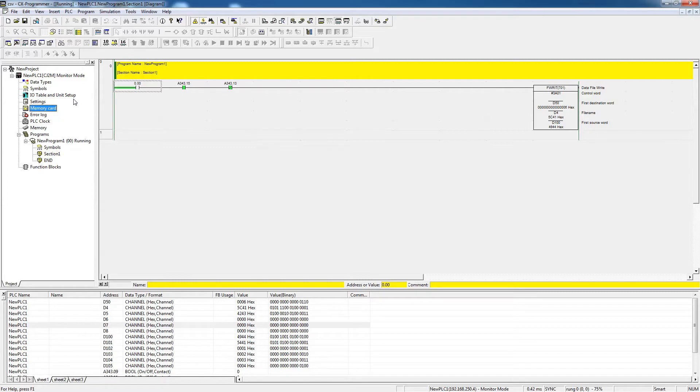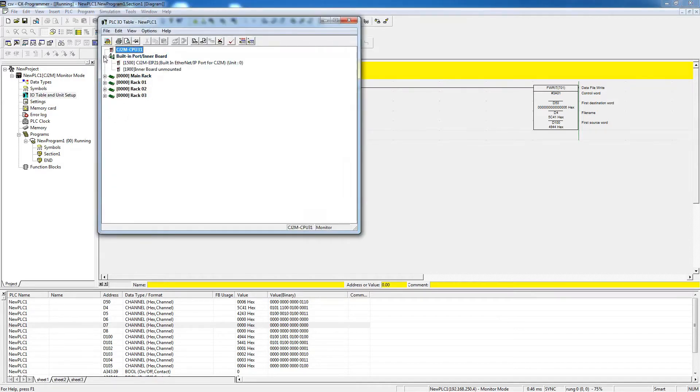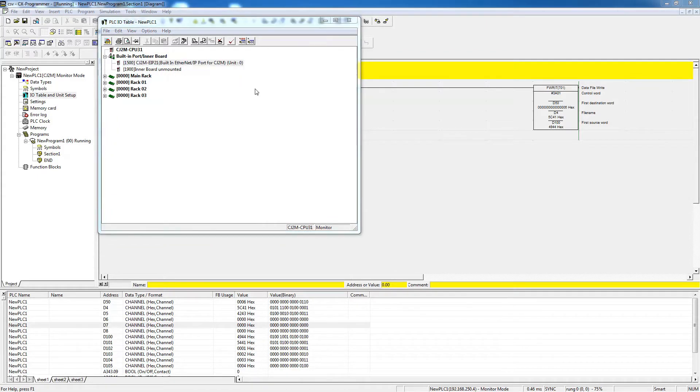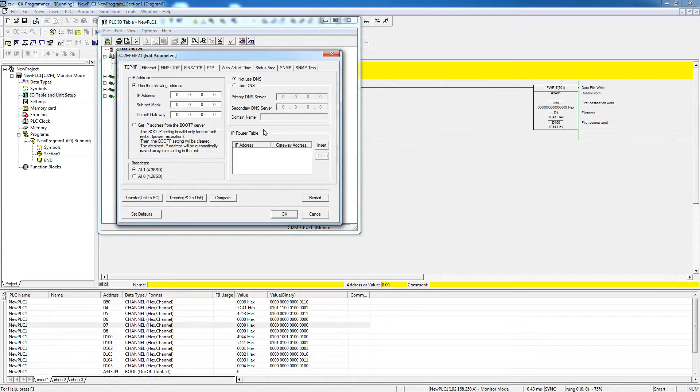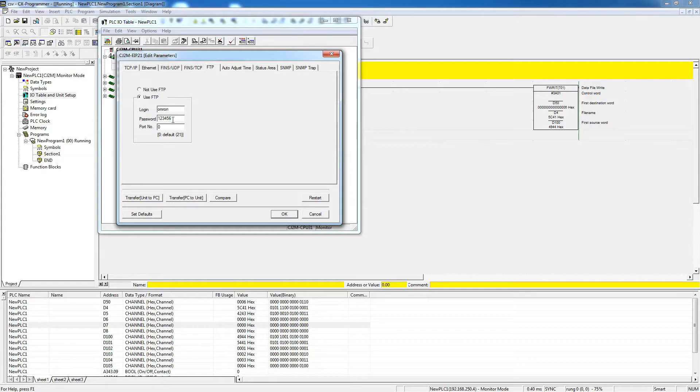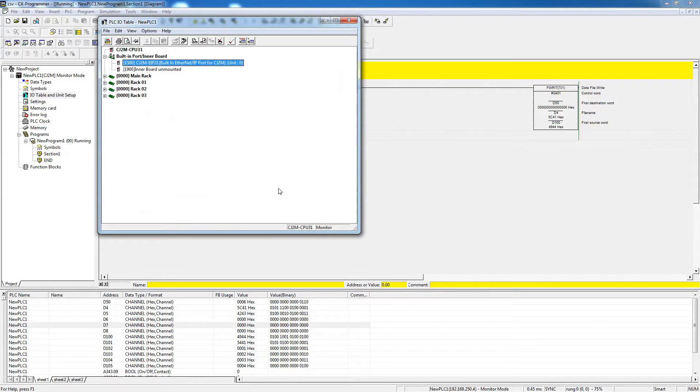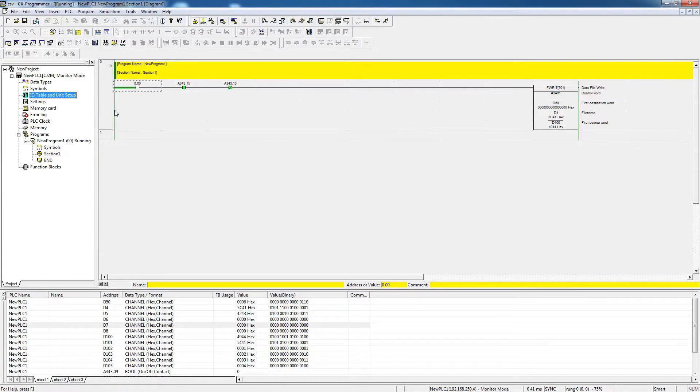If you want to have access to those stored files via FTP, then we want to enable that. To do that, you go to the IO table, double click on that, and then we want to go to the built-in Ethernet IP port. I'm going to double click on that, and then we get this window. In here we have a tab that says FTP, and as you see here, I already said that I want to use the FTP, and you have to give it a login and a password to use it, and then you can transfer to the unit from the PC to the unit, and then it will ask you to restart, so you can restart the unit, and that's all you have to do to enable the FTP.